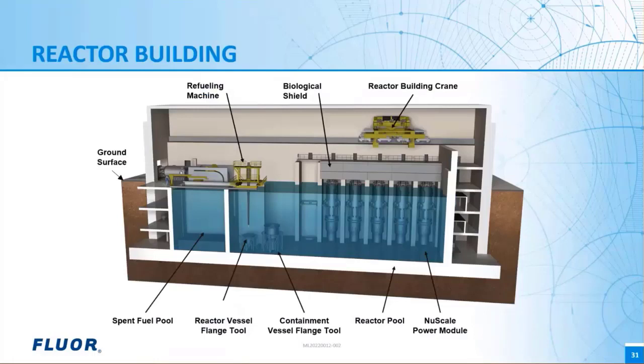You can see the reactor pool, which contains about 5.9 million gallons of water for the 12 module plant. Five of the 12 reactors are shown in this cutaway. The sixth reactor is disassembled. The lower containment vessel is unbolted and sitting in the containment vessel flange tool on the bottom of the reactor pool. This then allows unbolting of the reactor vessel, which you can see sitting in the reactor vessel flange tool.